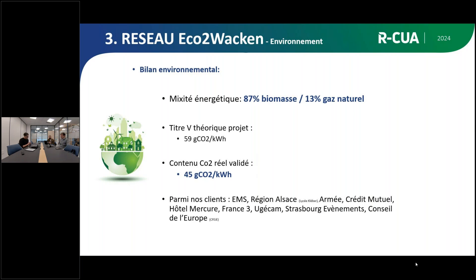D'un point de vue environnemental, le réseau est à 87 % de biomasse. On certifie les contenus CO2 de nos réseaux : on pensait être à 59 g de CO2 par kWh avant la mise en service, sachant que le gaz est à 234 g de CO2 par kWh. Le réseau du Wacken, remesuré chaque année, a été validé à moins de 50 g — soit 45 g de CO2 par kWh. Grâce à l'interfaçage avec la chaleur de récupération industrielle, on est en train de faire baisser drastiquement ce contenu CO2, qui va progressivement se rapprocher des 10 g de CO2 par kWh.